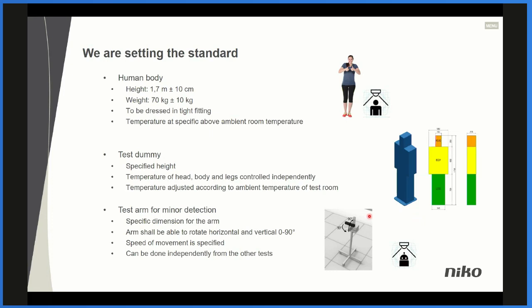Another test which can be done is a test for minor motion detection. Again, the specification for this arm is very strict, and it should be able to rotate both horizontally and vertically from 0 to 90 degrees. The speed of the movement is also very specified. And the good thing, at least for us as a supplier, is that this test can be done independently from the other tests. So you can actually have this test done in your own facility and only need to go to the laboratory for the other tests.